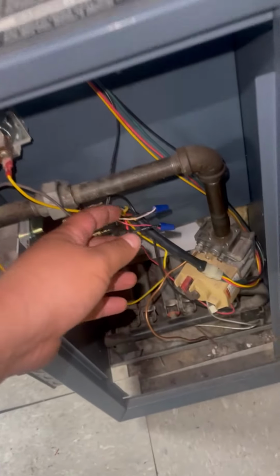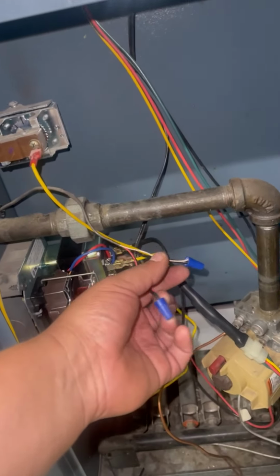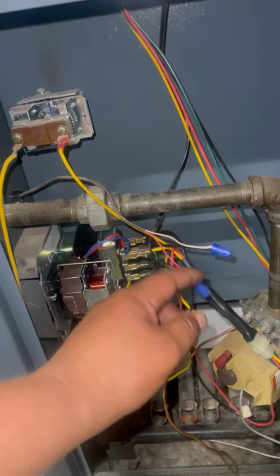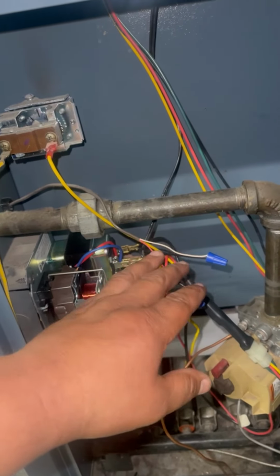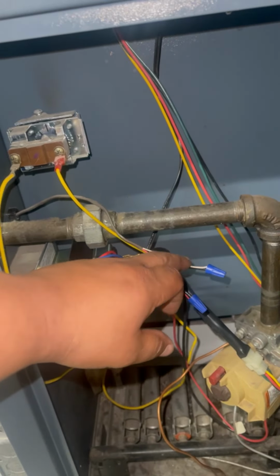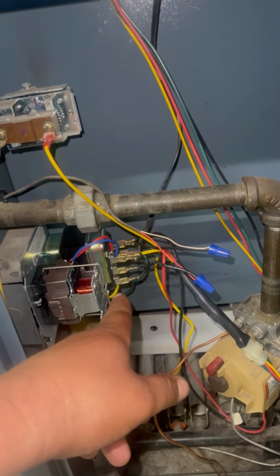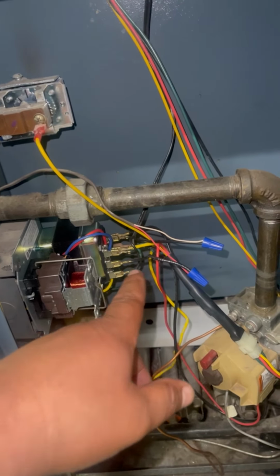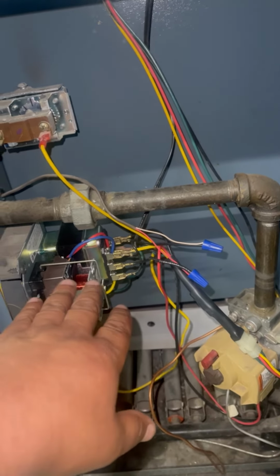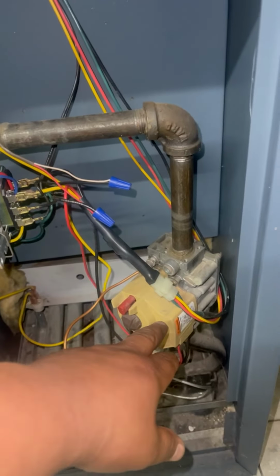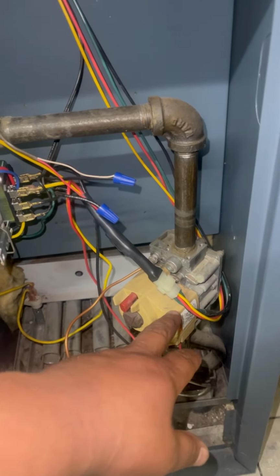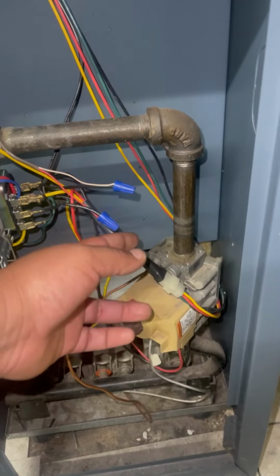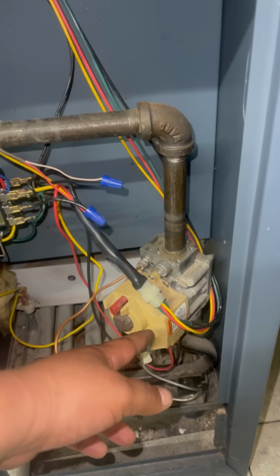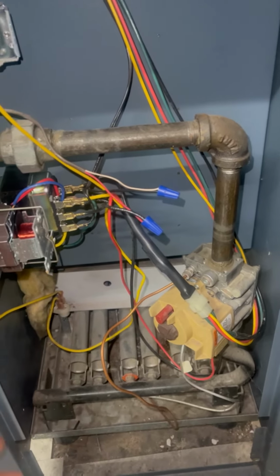2 red wires. This goes all the way down to this point. So I took my voltage meter. I checked for continuity on both these lines. I got continuity. So that tells me the end switch is working. Again, continuity. So this is supposed to be pulling in. So that's how I distinguished the problem was here. Also, I made sure there was no power going to the gas valve. There was no power because the circuit closes when the damper makes. So what I'm trying to say is process of elimination is very easy.